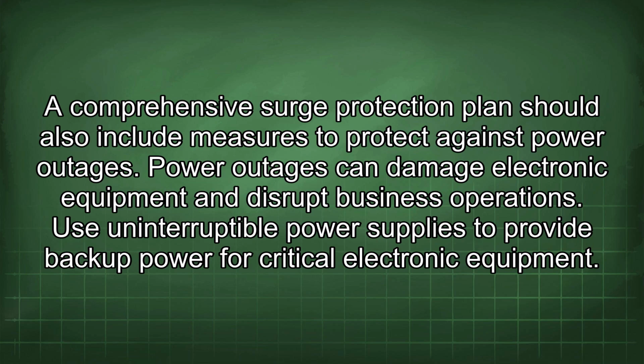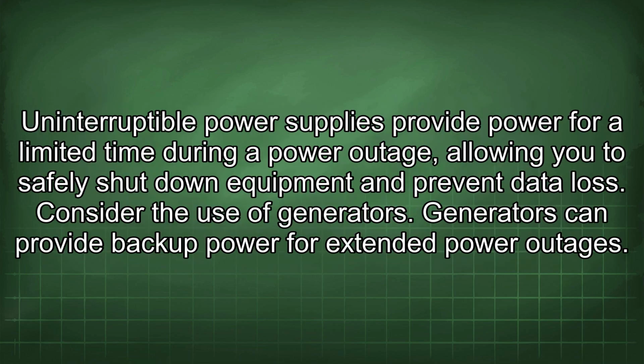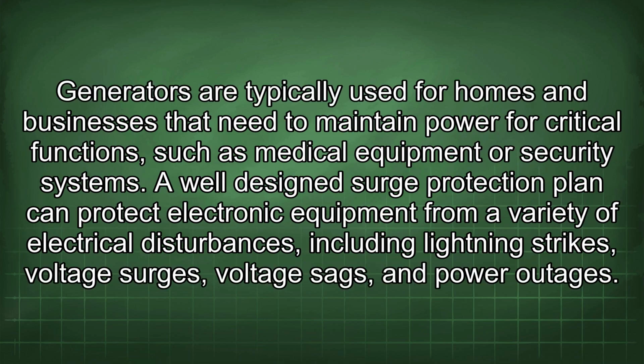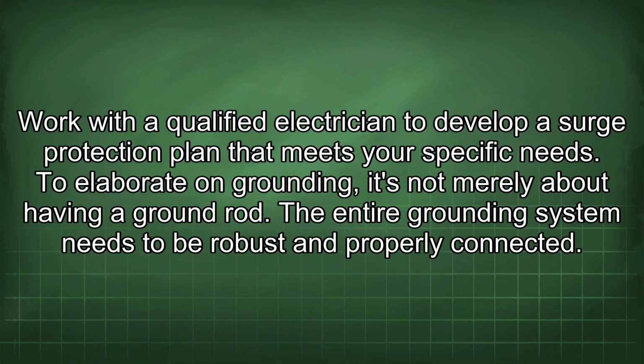Power outages can damage electronic equipment and disrupt business operations. Use uninterruptible power supplies to provide backup power for critical electronic equipment. Uninterruptible power supplies provide power for a limited time during a power outage, allowing you to safely shut down equipment and prevent data loss. Consider the use of generators. Generators can provide backup power for extended power outages. Generators are typically used for homes and businesses that need to maintain power for critical functions such as medical equipment or security systems. A well-designed surge protection plan can protect electronic equipment from a variety of electrical disturbances, including lightning strikes, voltage surges, voltage sags, and power outages. Work with a qualified electrician to develop a surge protection plan that meets your specific needs.